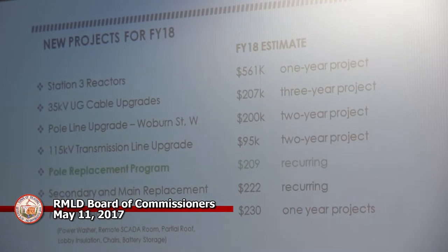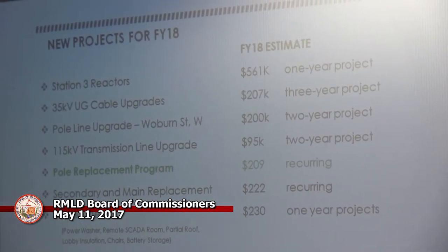The pole replacement program is recurring because, as you know, we test 10% of the poles in our jurisdiction area, which covers North Reading and half of Reading. We've got 6,400 poles, and every year we test 10%, about 640 poles. Depending on the results, the ones that fail we immediately replace — that's why you see those double poles. Some are still out there that we try to get to as soon as we can, and some marginally passed, so we're planning to upgrade those as we go. Every year we do more and more of those.